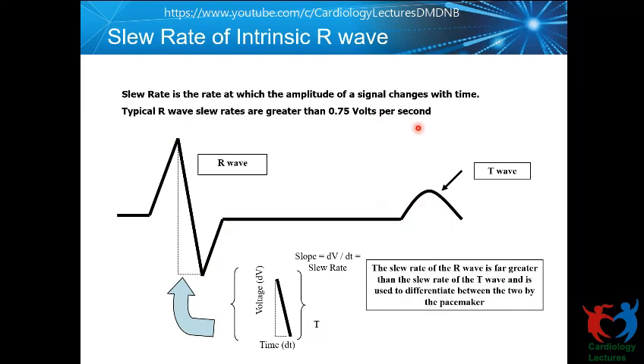So there is a band pass filter. This will allow a certain frequency of the waveform, which is typically of the waveform with respect to the R wave and P wave. So that is what it will allow to go through. And that filtering is based on the frequency characteristic of the waveform. That is related to the slew rate. So when the slew rate is higher, the frequency is higher. When the slew rate is lower, the frequency is lower. So there is no programmable parameter relevant to that.